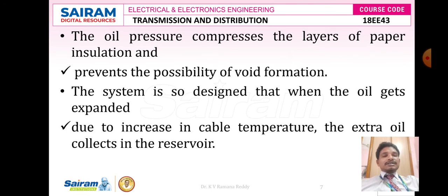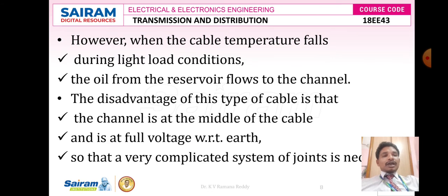The system is designed so that when the oil expands due to increase in cable temperature, the extra oil collects in the reservoir. However, when the cable temperature drops during light load conditions, the oil from the reservoir flows back to the channel. The disadvantage of this type of cable is that the channel is at the middle of the cable and is at full voltage with respect to earth, so that very complicated systems for joints are required. Wherever we have to increase the length of the transmission line, it is somewhat difficult to overcome the leakage of oil especially at the center of the core, which consists of an oil channel or oil ducts.